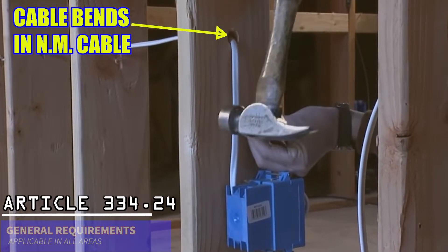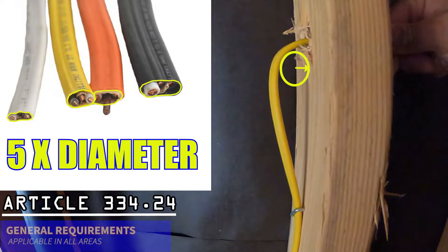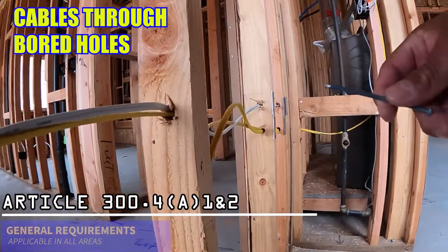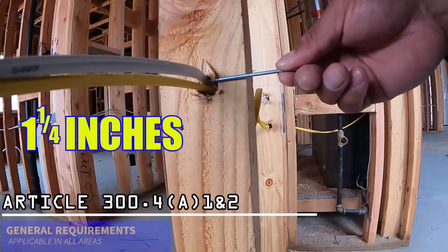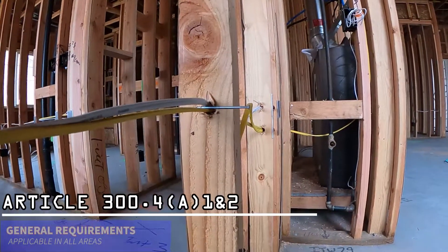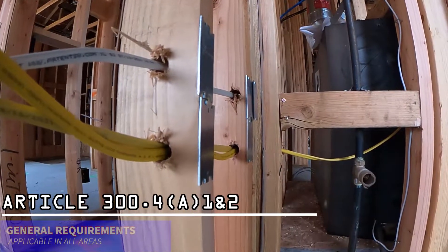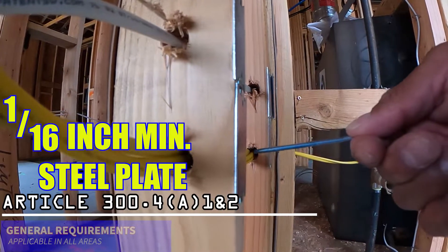Bends in non-metallic sheathed cable must be no less than five times the diameter of the cable. Bored holes for electrical cables should be maintained no less than one and a quarter inches from the face of the framing members. However, where bored holes are less than one and a quarter inch from the edge, protection from nail or screw penetration must be provided by a steel plate or bushing that is a minimum 1/16th of an inch thick.